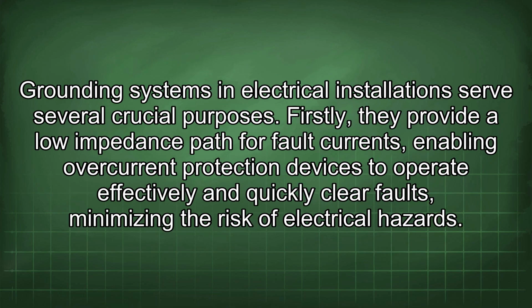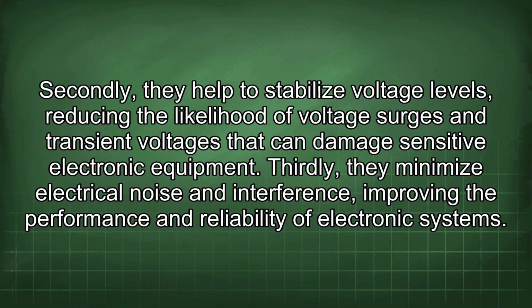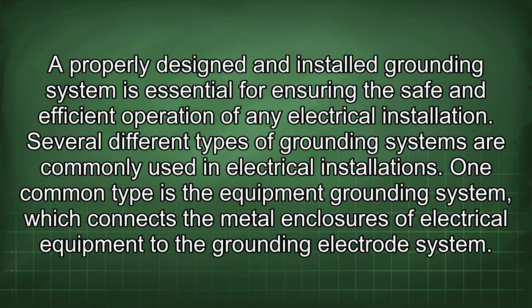Grounding systems in electrical installations serve several crucial purposes. Firstly, they provide a low impedance path for fault currents, enabling overcurrent protection devices to operate effectively and quickly clear faults, minimizing the risk of electrical hazards. Secondly, they help to stabilize voltage levels, reducing the likelihood of voltage surges and transient voltages that can damage sensitive electronic equipment. Thirdly, they minimize electrical noise and interference, improving the performance and reliability of electronic systems. A properly designed and installed grounding system is essential for ensuring the safe and efficient operation of any electrical installation.